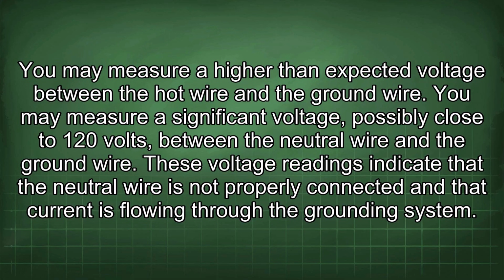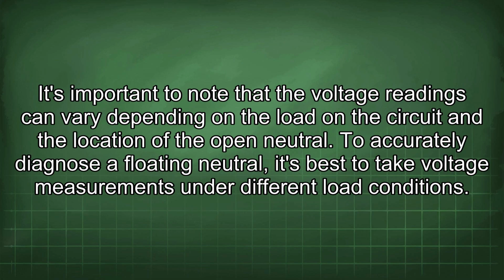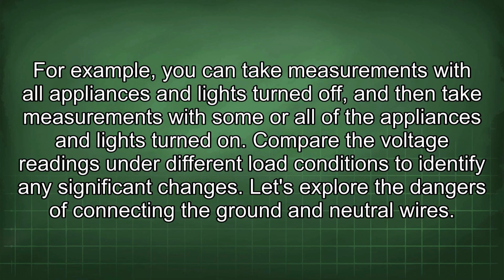These voltage readings indicate that the neutral wire is not properly connected and that current is flowing through the grounding system. It's important to note that the voltage readings can vary depending on the load on the circuit and the location of the open neutral. To accurately diagnose a floating neutral, it's best to take voltage measurements under different load conditions. For example, you can take measurements with all appliances and lights turned off, and then take measurements with some or all of the appliances and lights turned on. Compare the voltage readings under different load conditions to identify any significant changes.